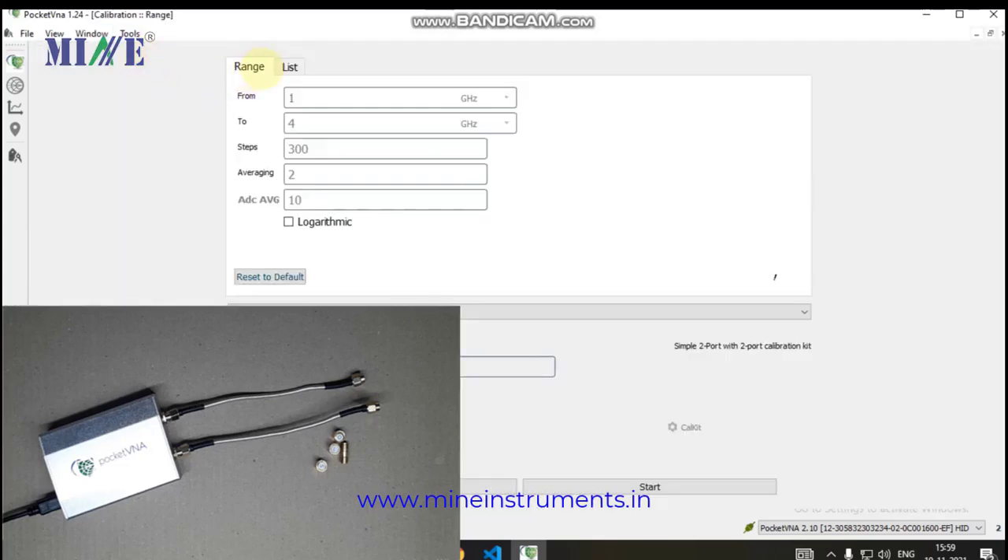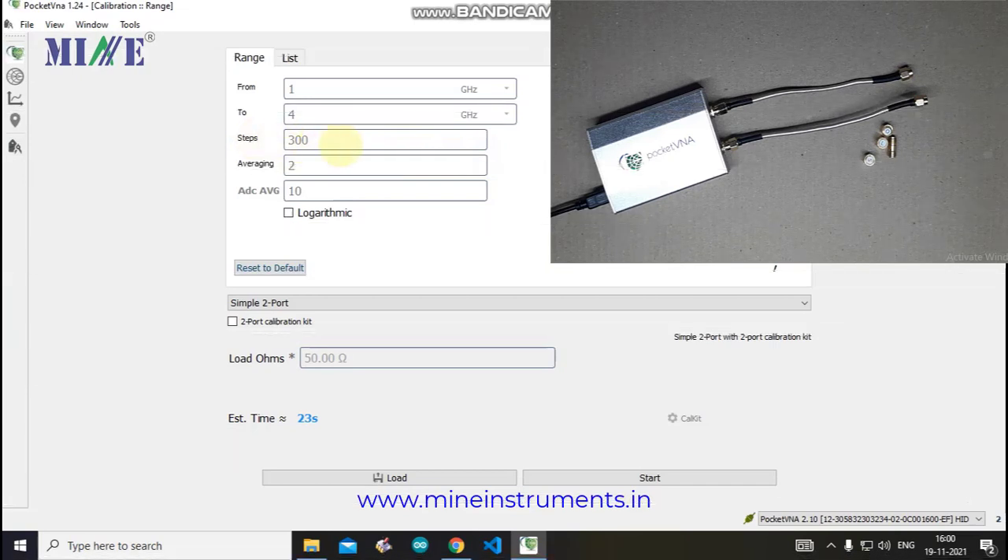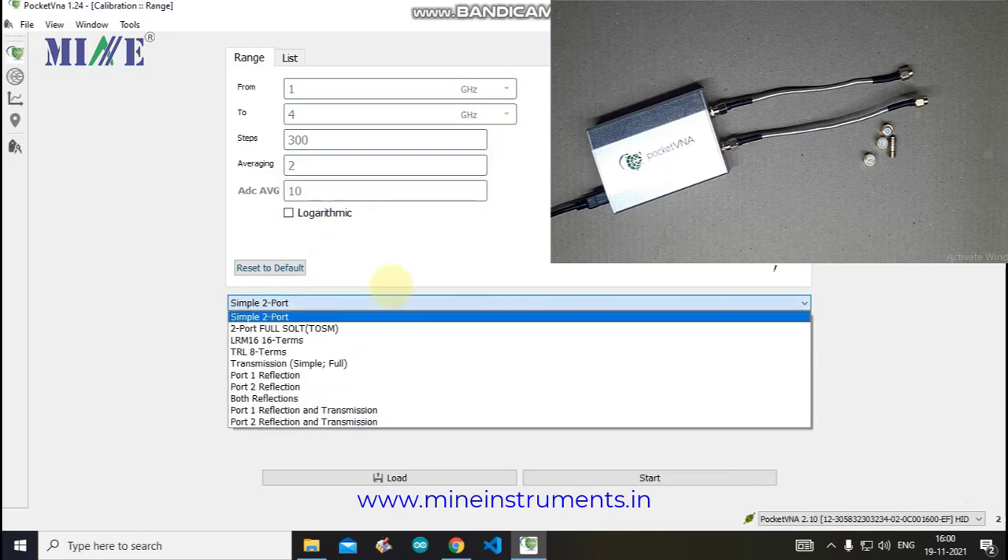Select Tools in the menu bar and go to Calibration. In the calibration window, select the calibration parameters. The Pocket VNA can work from 500 kHz to 4 GHz. You can select the desired frequency range as per your application. Steps show discrete samples within the range. ADC average should be set to 10, and software average to 2. Higher average values will increase accuracy but consume more time during calibration and operation.